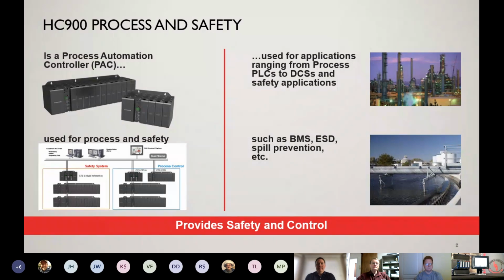Two ways that we typically do that is, one, we either tie the HC900 with the communication output to an RM7800 series, which manages the burner safety, or we've done applications on large boilers, large utility boilers, where we actually have implemented the burner management directly into the HC in the SIL 2 processor, and then we've used the industrial flame monitoring sensors for UV and IR detection, providing a signal back into the HC900 rack.